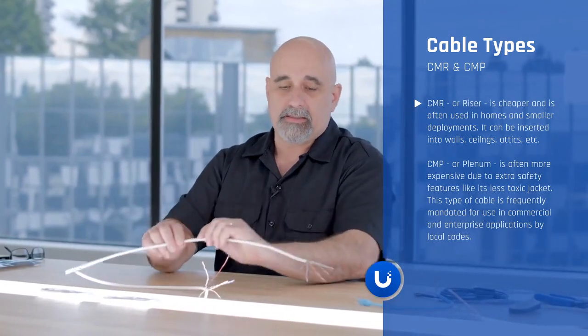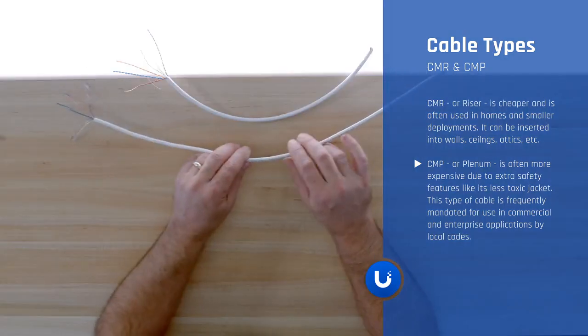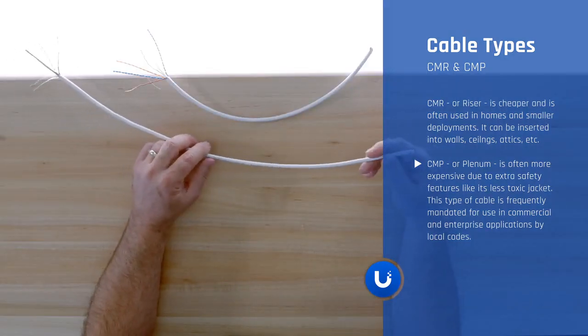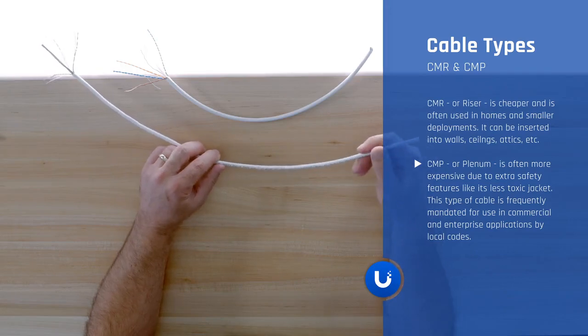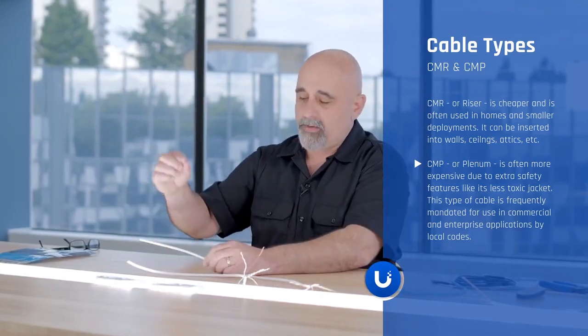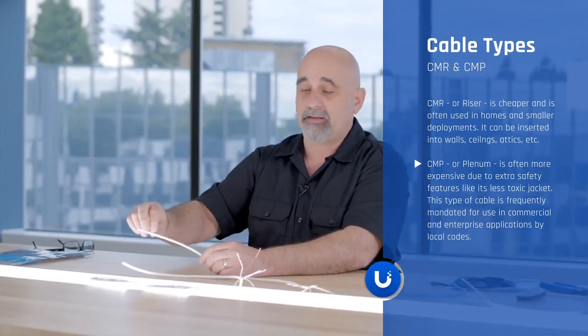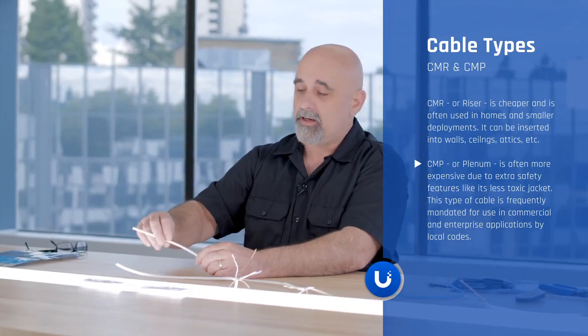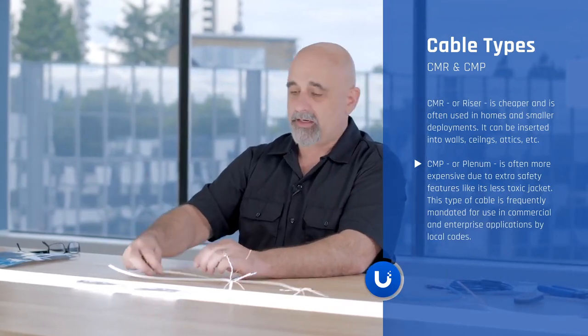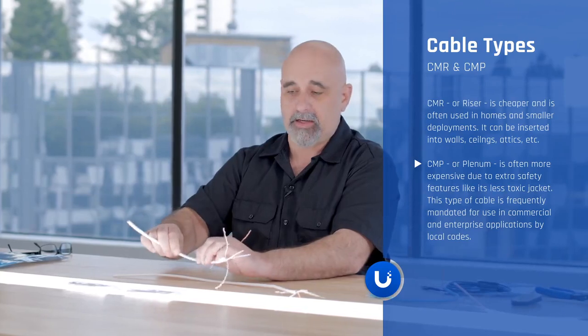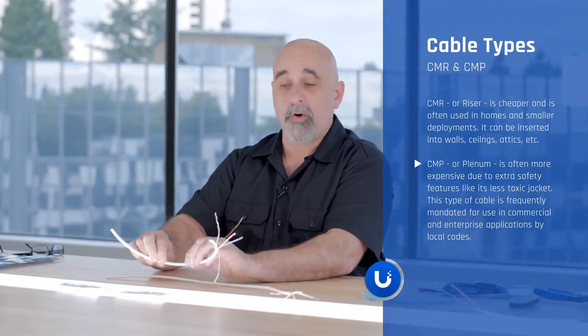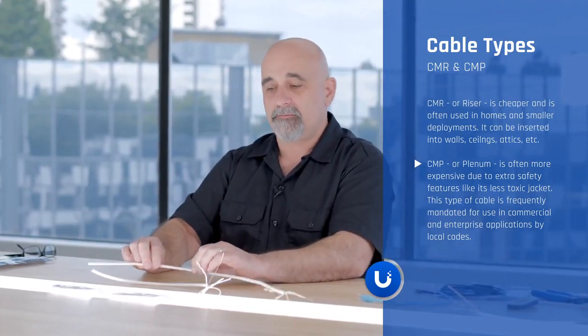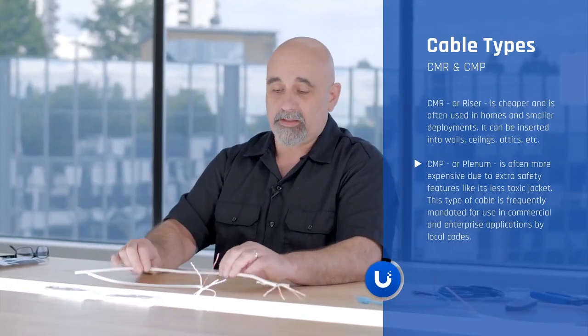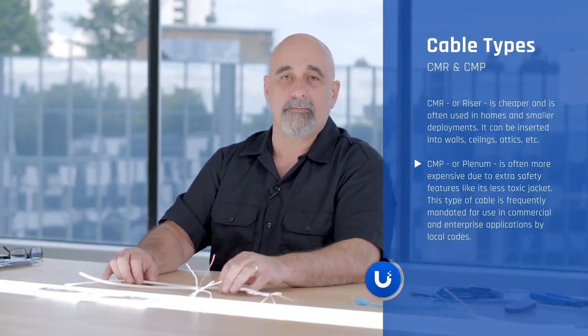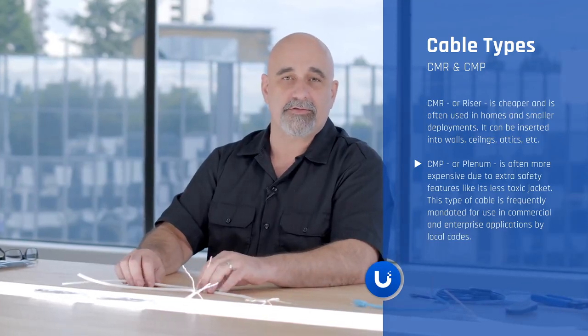The other type is CMP, or plenum. The jacket that is used on it has been specifically built and tested to not release a number of toxic fumes in cases of a fire. Many times within a building, if there's a fire and the cable starts to catch fire, this is not going to release many of the toxins that you're going to find in a PVC rated coating of a CMR cable. It's a little bit more expensive, but we make a standard that we always install plenum rated cable. It's the safest way to go, and you don't have to ask questions for local code.